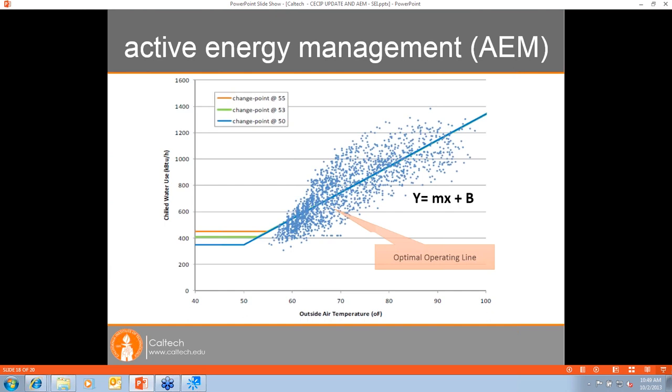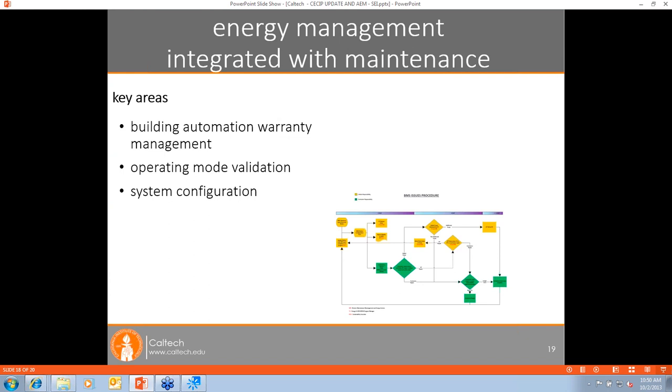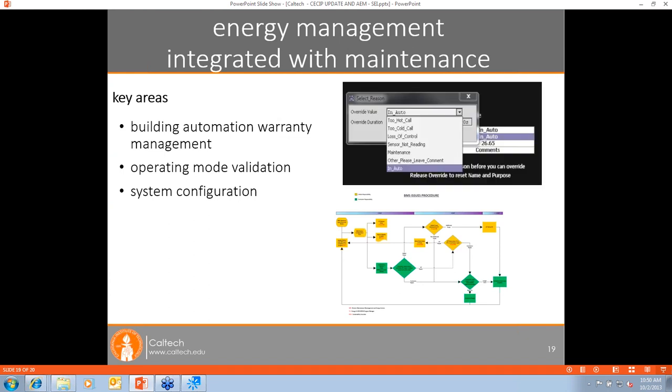Here's another example. Most of these building-controlled retrofits we do now are more complex than an old pneumatic building. So there's electronics. There's all kinds of elaborate engineering sequences to say, shut the system down at 4 p.m. And if it's midnight, purge the air a little bit. And if there's an occupancy sensor that switches on and off, delay it for a half hour before you turn it back on. So there's a lot of configuration and thought that goes into this. Well, this chart here is just a snapshot of the operator interface. If you go back to your campus, you can try to ask the questions about, how are we tracking configuration changes to these systems?